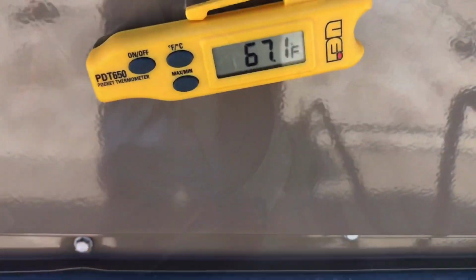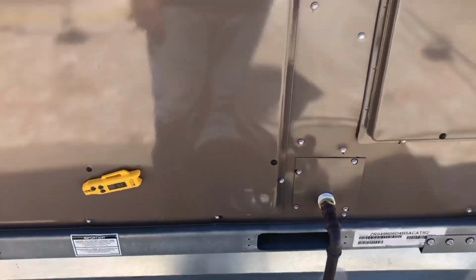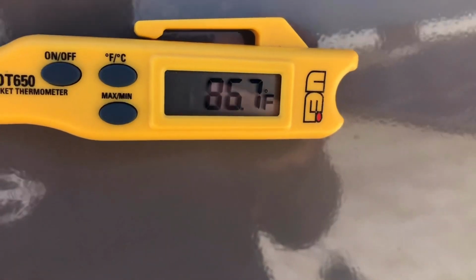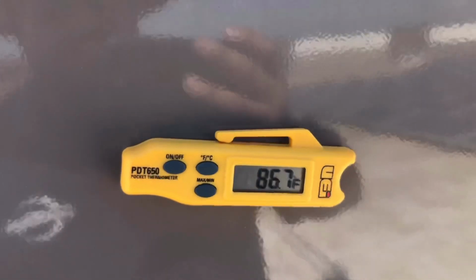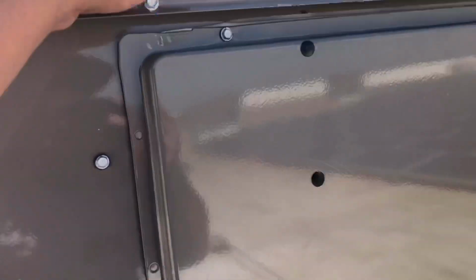Oh yeah? Got about 67 degree supply air. Let's go ahead and check over here on the return air. Return air, we're looking at about 87. So 87 and 67. Looks like we got a 20 degree split. That looks pretty good. Let me show you the pressures real quick.